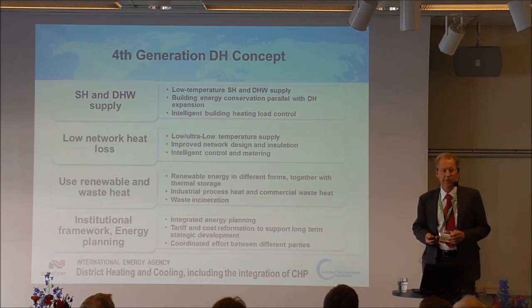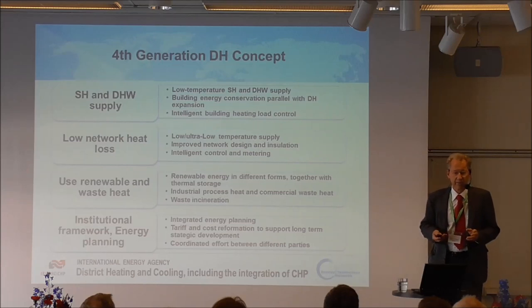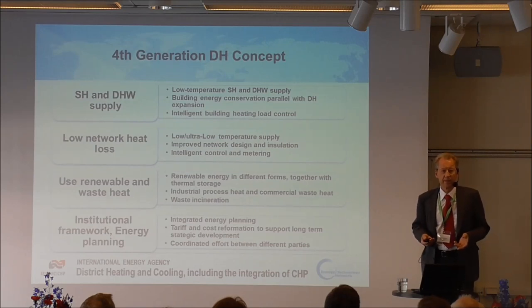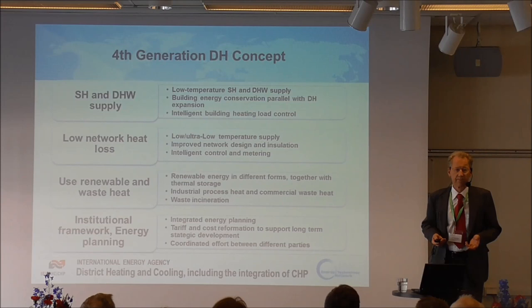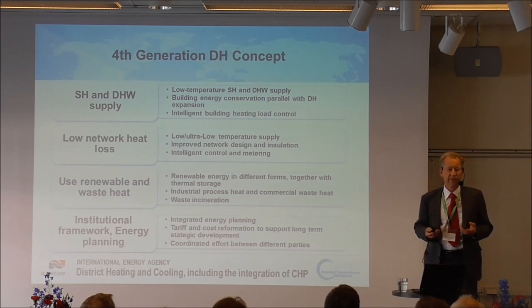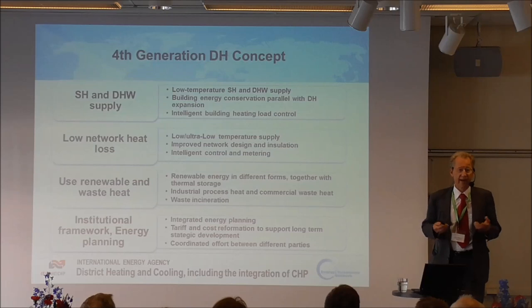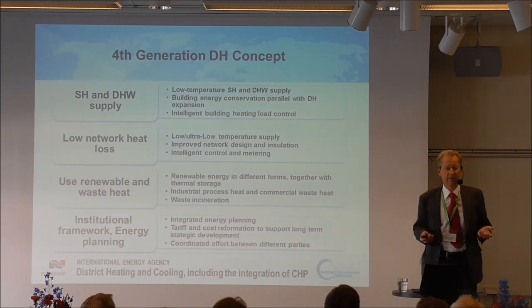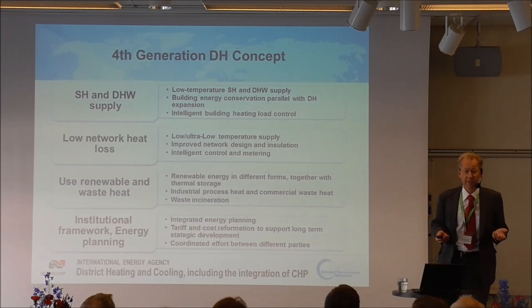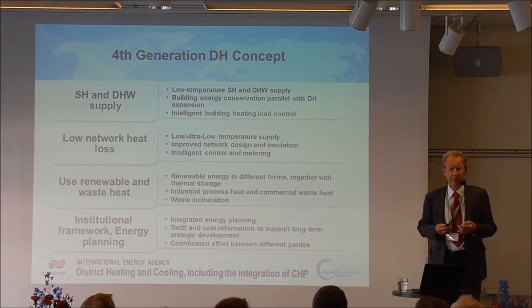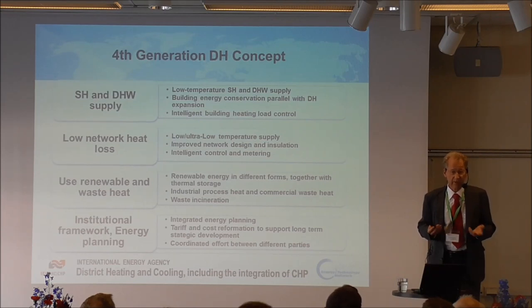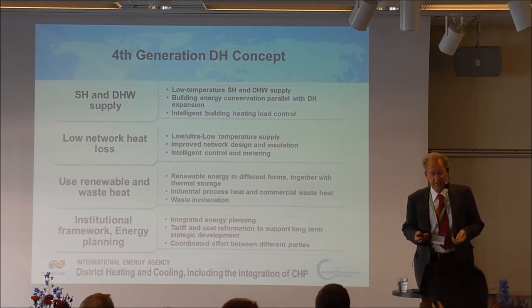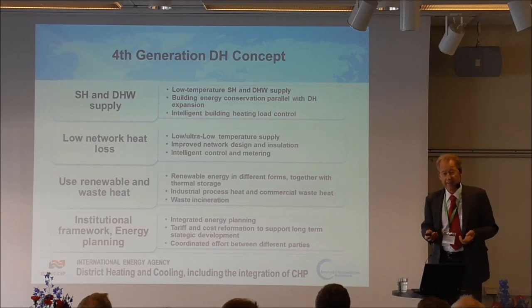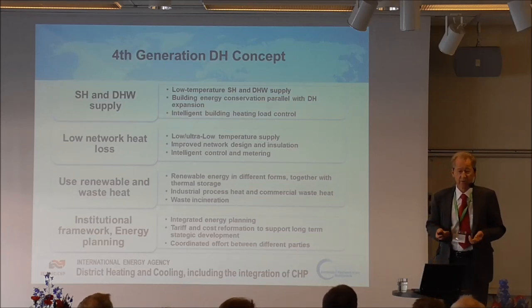Good engineering in future is to find the real minimum size of pipes, because if you just make it a little bigger, you have much more heat loss than you need. Insulation of pipes is very difficult - you can add more insulation, but you also add more area, and you'll have almost the same heat loss. So what really helps is minimizing the internal pipe sizes. Then you can minimize heat loss without any cost, even cheaper. It's mainly about understanding that the energy you need to transfer is only so small, and therefore you can do that, along with having some kind of robust solution.